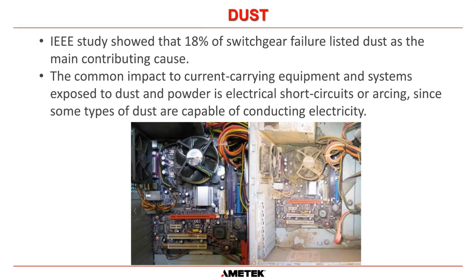Another thing that people get a little bit blasé about, or they don't take as seriously as they should, is dust. The IEEE study that was done a few years ago showed that 18% of all switchgear failures listed dust as the main contributing cause. So that is basically 20%, so one out of every five failures in switchgear could be listed down to dust. And these pictures on this page here show you, I think it's actually a computer system, but you can see on the right-hand side, this one here, how dusty it is.